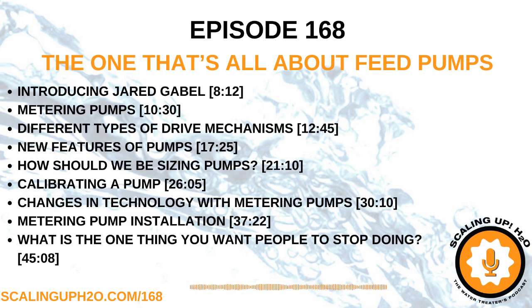Yes. So one of the weirdest things I've seen has to do with the installation of the suction line coming into the pump. You're probably familiar with not just dosing pumps, but a complete dosing system. It could be two or three pumps on a skid, and then a control panel or valves and such. What I've seen in the past as a problem is a pump that requires, and this will come from the manufacturer, a suction and discharge of maybe an inch pipe or a 3/4 inch pipe.